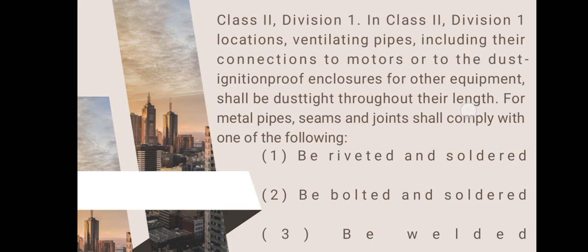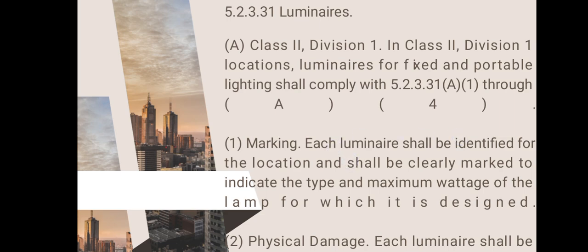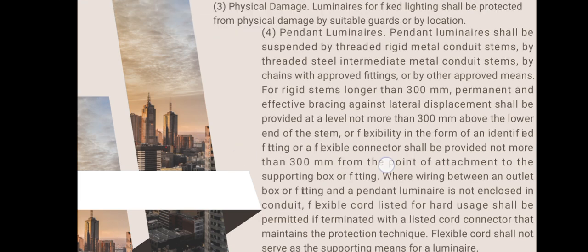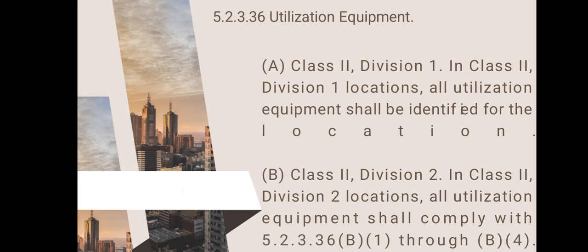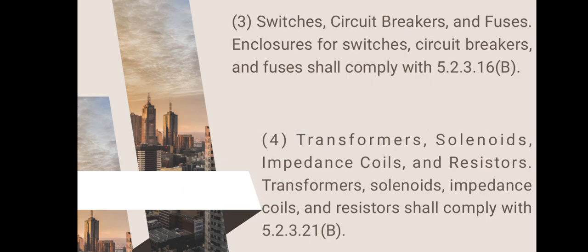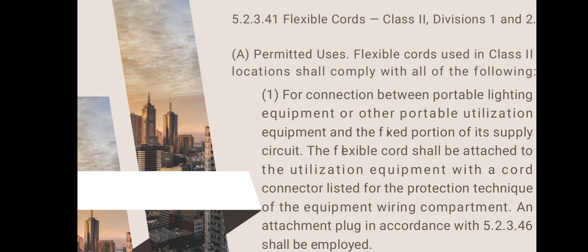So for the receptacles and attachment plugs, receptacles must be part of the premises wiring. Attachment plugs must provide connection to the equipment grounding conductor. Signaling, alarm, remote control, and communication systems. For these, switches, circuit breakers, and contacts must have enclosures identified for the location. Resistors, transformers, and other heat generating equipment must have enclosures identified for the location.